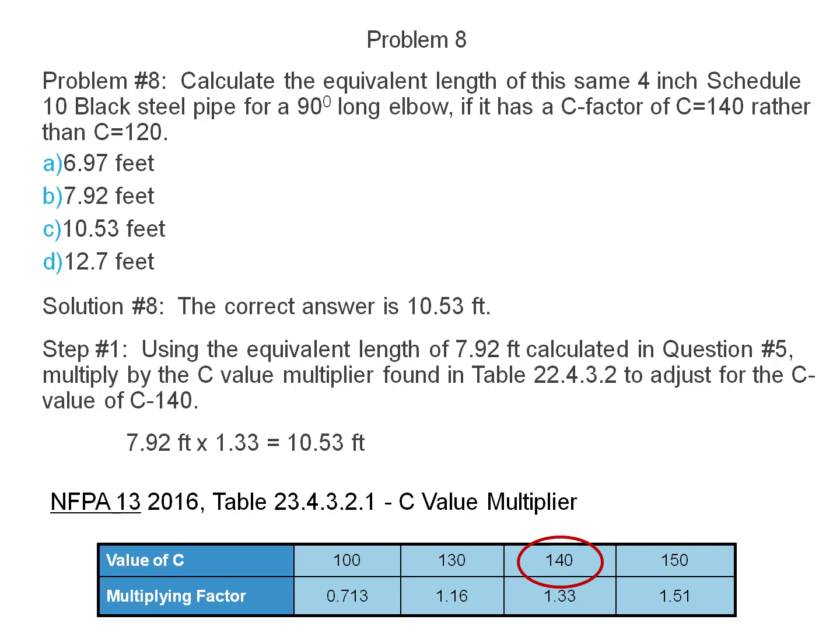Using the equivalent length of 7.92 feet calculated in question number 5, multiply by the C value multiplier found in table 23.4.3.2 to adjust for the C value of 140. 7.92 feet times 1.33, the factor, is equal to 10.53 feet.